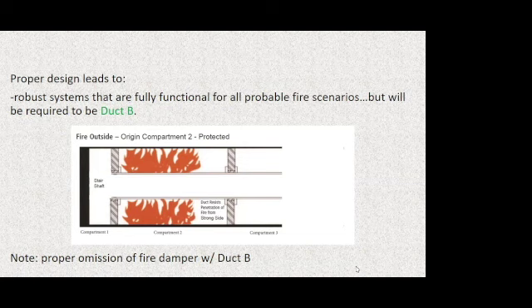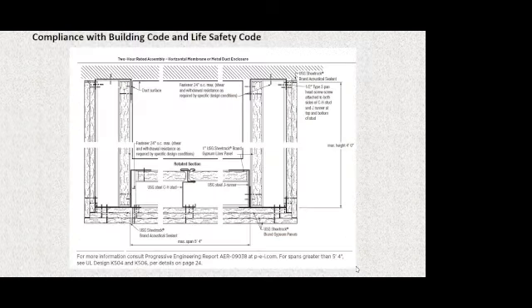And this could be any compartment using the pressurization method or the exhaust method. It's just the stair pressurization system that has the most confusion. And we'll talk about that as well. So when we omit that damper, we need to use what they call in the fire-rated duct industry, most common designs out there are going to be ISO tested designs. And ISO 6944 describes the test specimen that allows you to omit that damper as duct B. We're going to talk about exactly what duct B means.